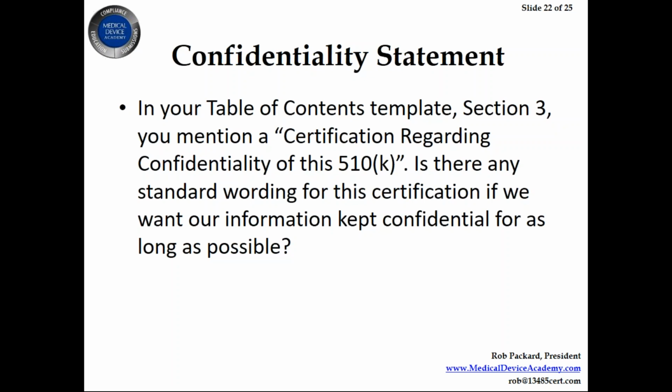Now if you read carefully through what my document says, it says that if you show this product at trade shows and marketing other events publicly, then the FDA has to be notified, so they're going to be able to divulge that yes, you've got a 510K pending. And I haven't ever known somebody that's actually done that, but you have to be very, very careful when you're at trade shows talking about a product that's 510K pending.